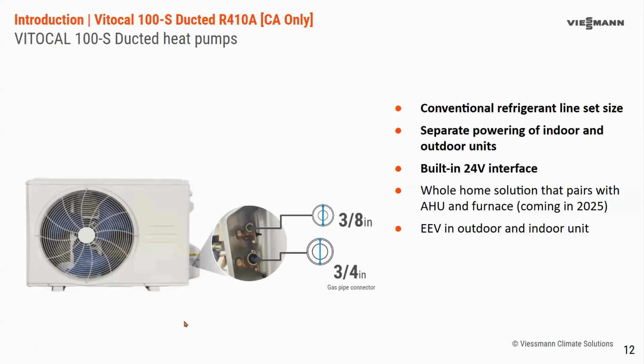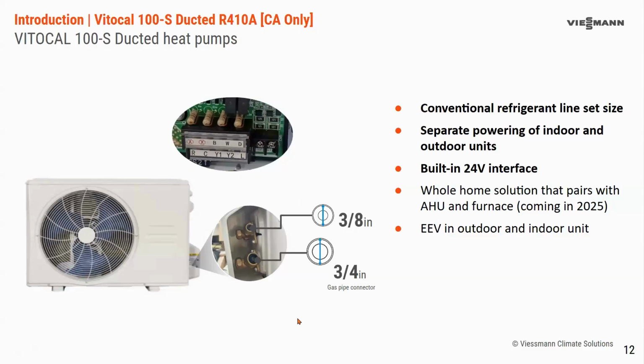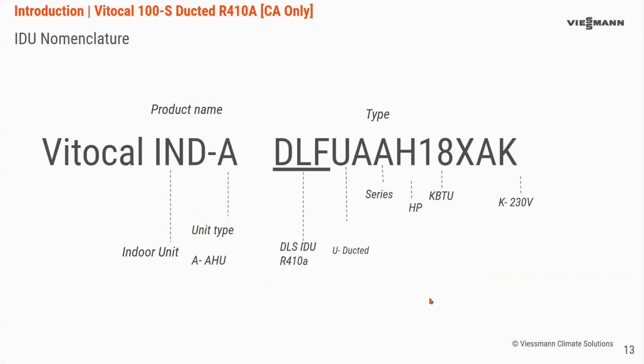So there are your line sets. You can see it's 3/8, 3/4 instead of 1/4 inch and 3/8. And there are your different connections. S1 and S2 is for your RS-485, your full communication. In the event that your indoor unit does not have full communication, or for whatever reason you want to wire it 24 volt, these are your terminals here for your 24 volt connections.